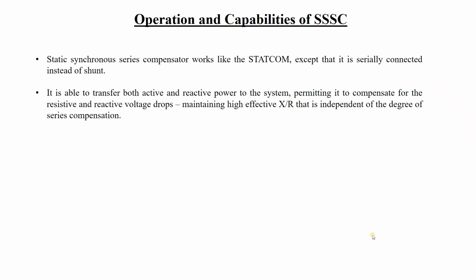It is able to transfer both active and reactive power to the system, permitting it to compensate for the resistive and reactive voltage drops. So similarities are there, because in STATCOM we have seen it is shunt connected, similar to the SVC, but in SVC the current was not controlled at low voltages, current was decreasing, but in STATCOM it is constant.